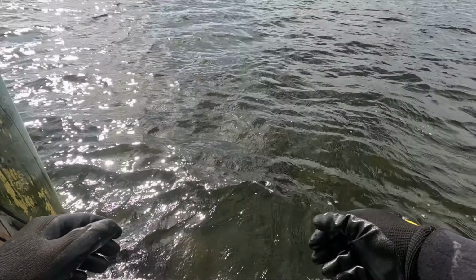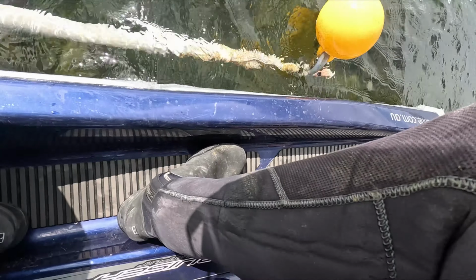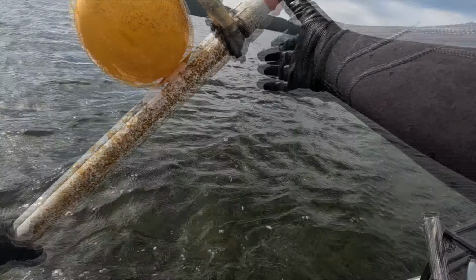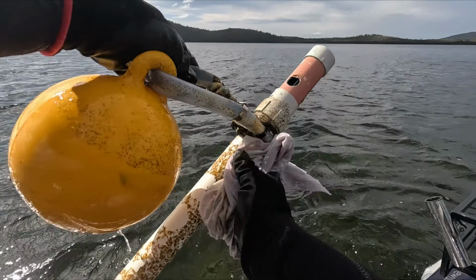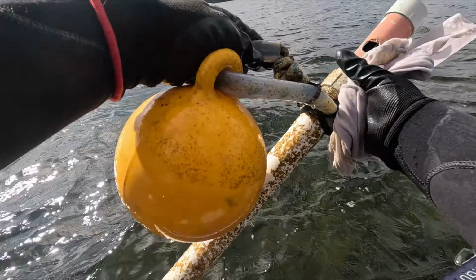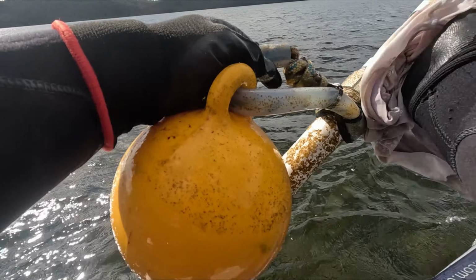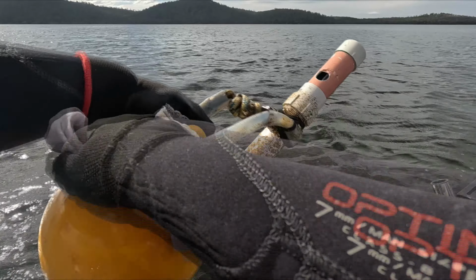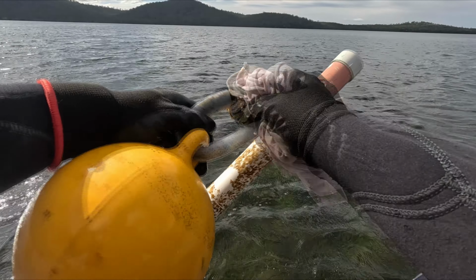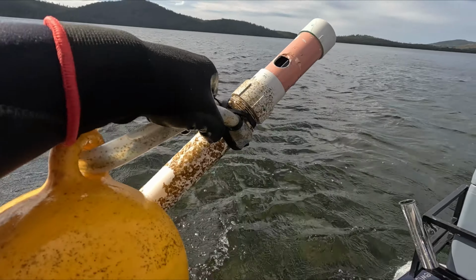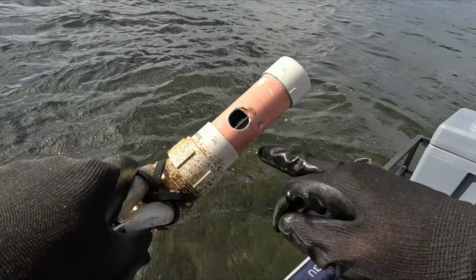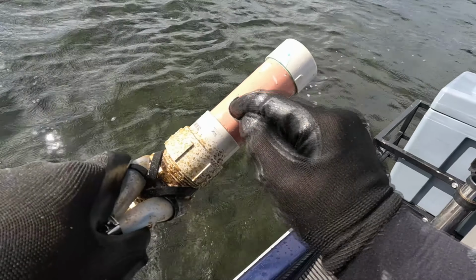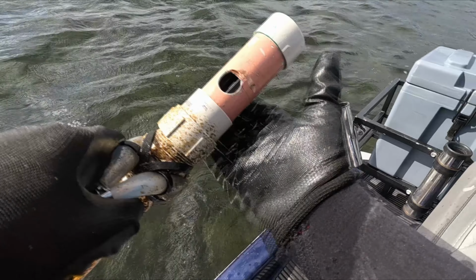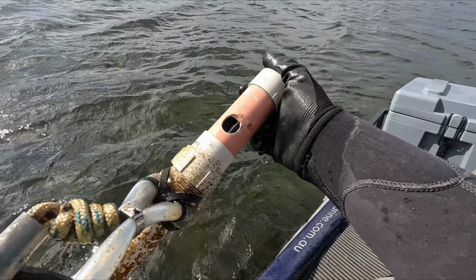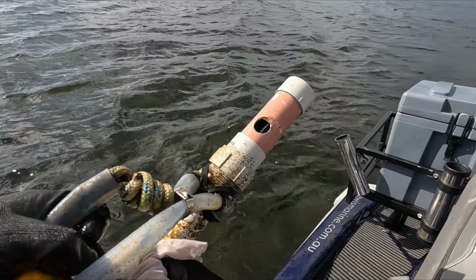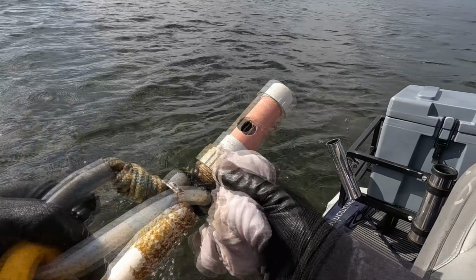Okay, next we're going to clean the sensor arm. Just bring that out of the water. What we're looking for here is just to clean off any of the loose stuff on the arm, the sensor cap, and the float. This one's in pretty good nick, there's not a lot growing on it. What we want to do is look at inside of here that we've got a nice clean throat. That's the sensor inside of there. Just make sure that's clean, free of any debris. If it's clean, then there's not much more for us to do. We can put that back in the water. It should be right to go.